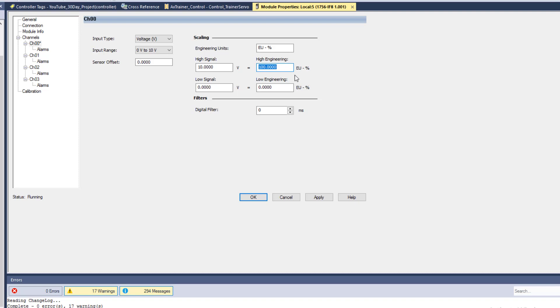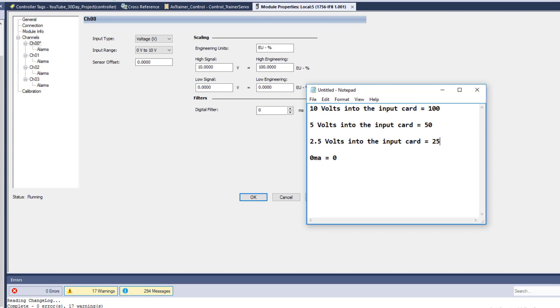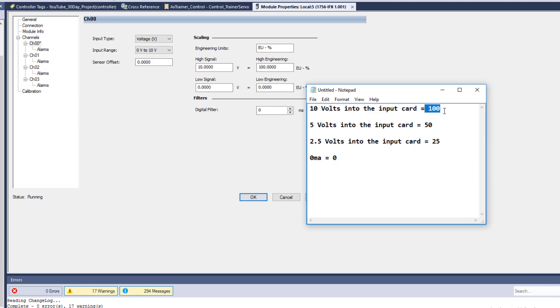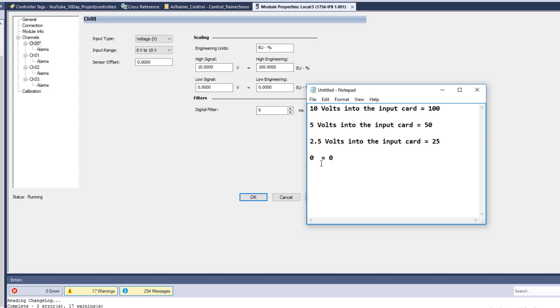To make this concrete: if I have 10 volts to my input card from the field device, it's going to be 100%. If I have 5 volts it's going to be 50%. If I have 2.5 volts it's going to be 25%. If I have zero volts it's going to be zero. That's an easy way to understand the scaling.